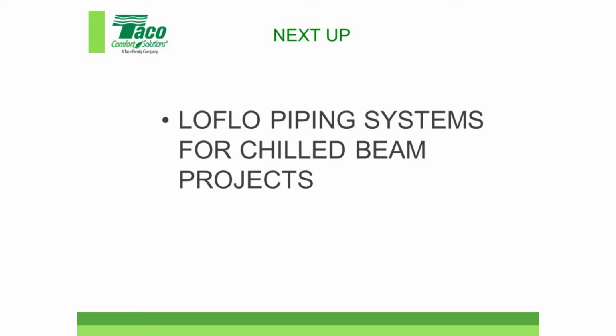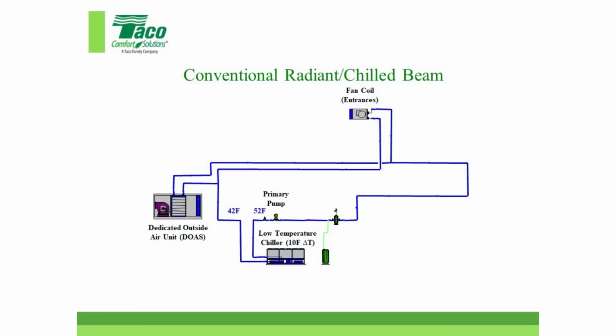All right. On the brochure it says ways to save money with this type of system. So the rest of it was kind of an introduction to radiant cooling. This is a different type of piping system, a different thought process. Your traditional cooling system is different than a heat pump system. Here's your low temperature chiller, with a 10-degree delta T, 12 degree, 14 degree, whatever it is, delivering cold water to the area. Fan coils, dedicated outside air, couple of pipes, boom.